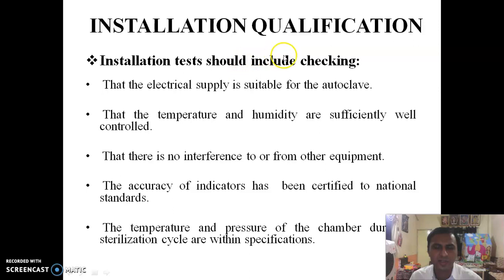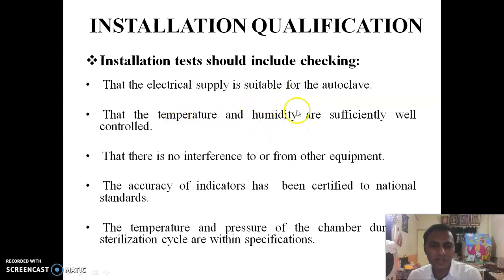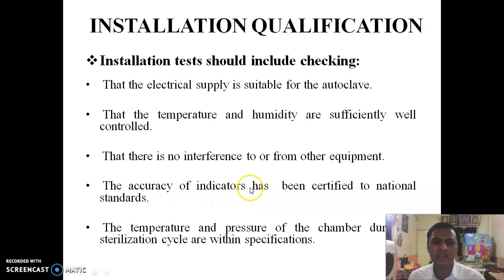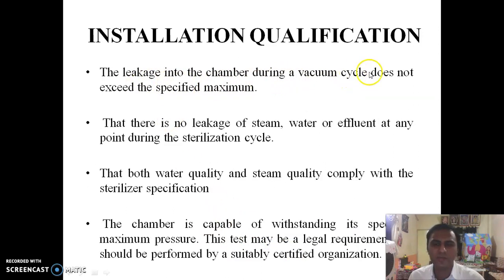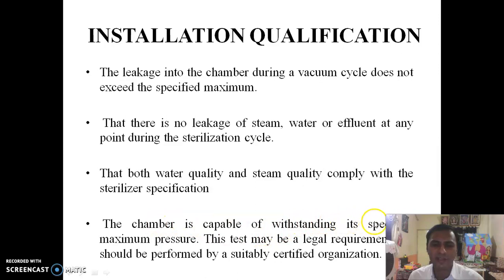Installation qualification should include checks that: the electrical supply is suitable for the autoclave; temperature and humidity are sufficiently well controlled; there is no interference with other equipment; accuracy of indicators has been certified to national standards; temperature and pressure of the chamber during a sterilization cycle are within specifications; leakage into the chamber during a vacuum cycle does not exceed the specified maximum; there is no leakage of steam, water, or effluent at any point; water quality and steam quality comply with sterilizer specifications; and the chamber is capable of withstanding its specified maximum pressure.